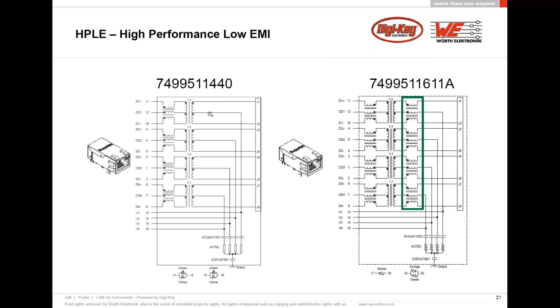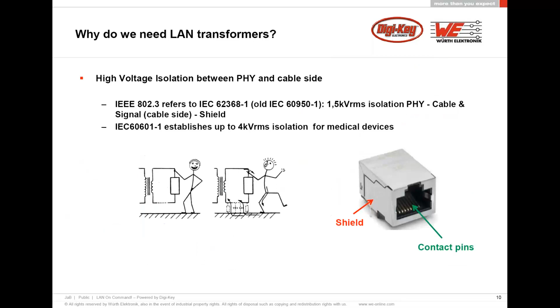As I said before, basically the differences are in the core material and also the wire - the wire becomes thicker. We can also see this on one of the first slides I showed you guys. On one side, this is a PoE plus transformer - you can see the core, as opposed to this core here, is much thicker, and the wire is also much thicker. Maybe the picture is not so sharp, but you can see the wire here is much thicker than the wire here. So, basically, one, the wire is thicker, and two, the core is made of a different material with a higher permeability.